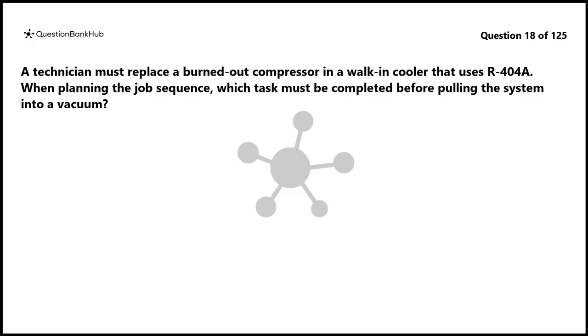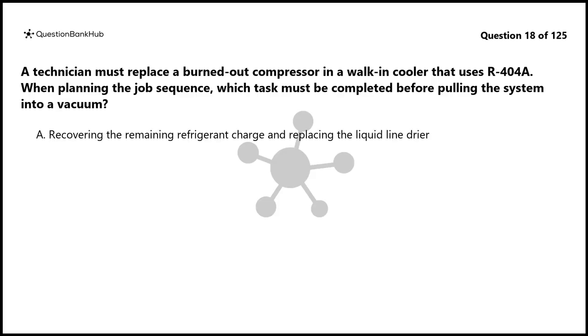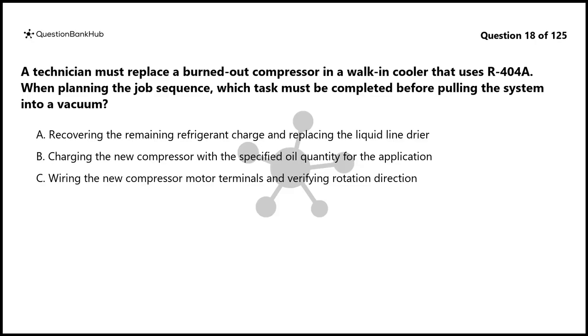Question 18. A technician must replace a burned-out compressor in a walk-in cooler that uses R404A. When planning the job sequence, which task must be completed before pulling the system into a vacuum? A. Recovering the remaining refrigerant charge and replacing the liquid line dryer. B. Charging the new compressor with the specified oil quantity for the application. C. Wiring the new compressor motor terminals and verifying rotation direction. D. Installing the new filter dryer and confirming all connections are leak-tight.